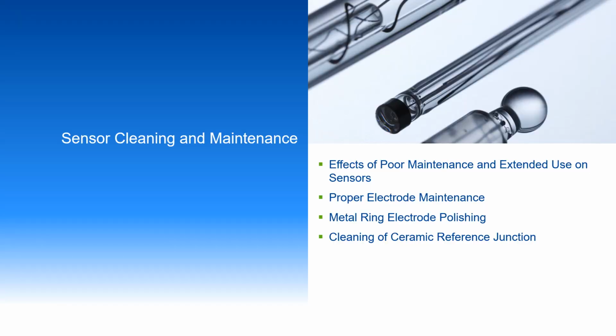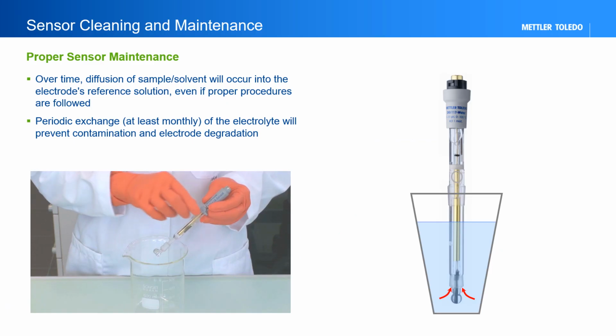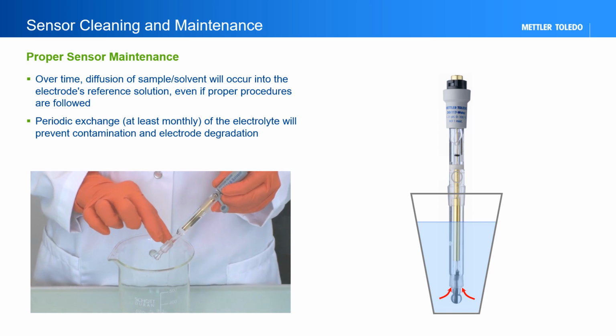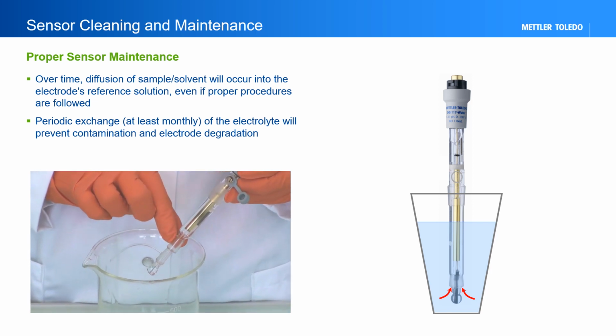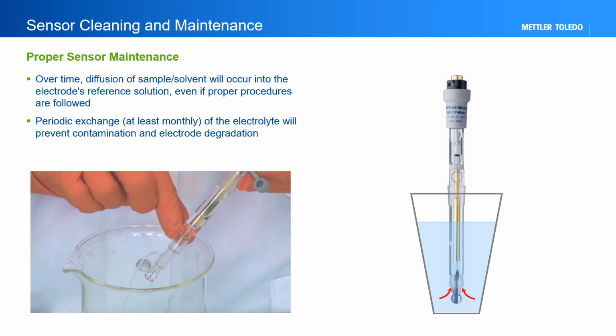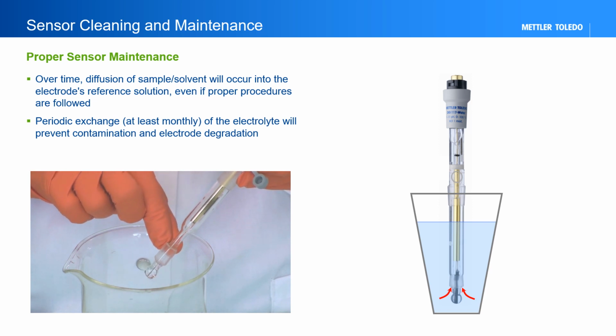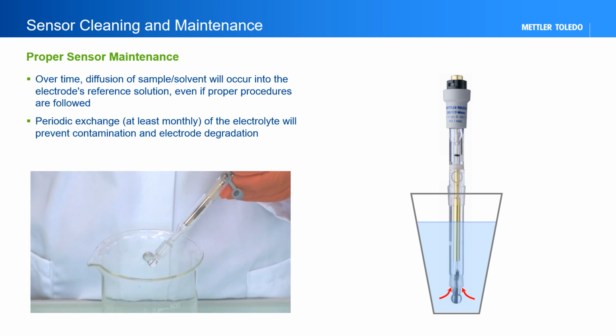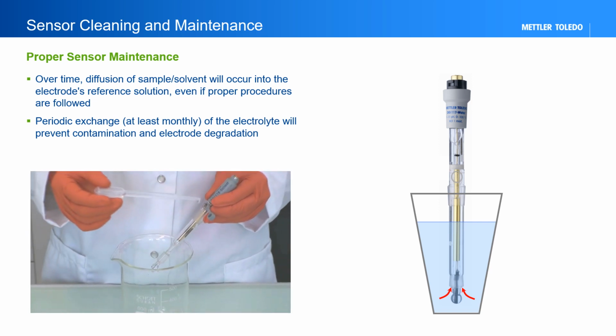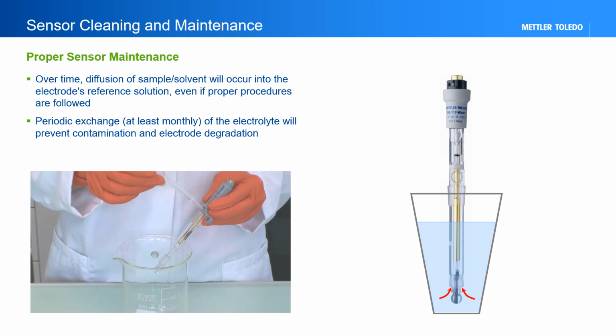The following section describes proper sensor cleaning and maintenance. Over time, even if the procedures are followed regarding the reference electrolyte level and fill port opening, the reference electrolyte will become contaminated. It is suggested to remove the reference electrolyte and exchange it once per month with normal use to avoid overall contamination and increased concentration of the reference electrolyte from slow evaporation of the solvent.